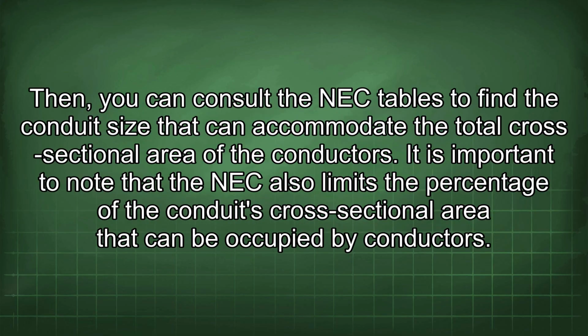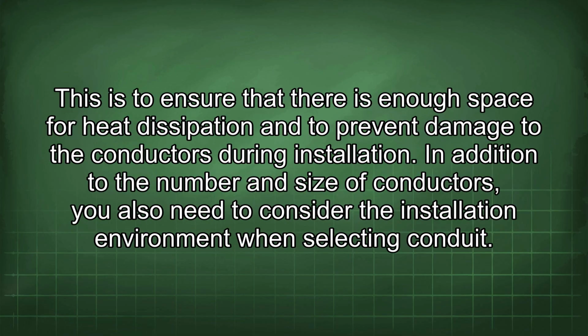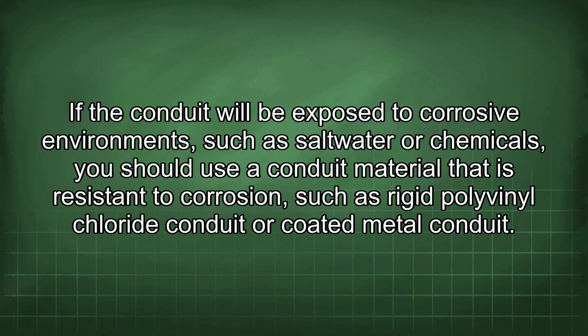Then, you can consult the NEC tables to find the conduit size that can accommodate the total cross-sectional area of the conductors. It is important to note that the NEC also limits the percentage of the conduit's cross-sectional area that can be occupied by conductors. This is to ensure that there is enough space for heat dissipation and to prevent damage to the conductors during installation. In addition to the number and size of conductors, you also need to consider the installation environment when selecting conduit. If the conduit will be exposed to corrosive environments such as saltwater or chemicals, you should use a conduit material that is resistant to corrosion, such as rigid polyvinyl chloride conduit or coated metal conduit.